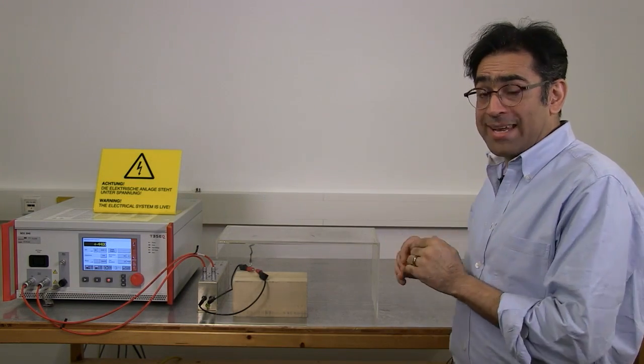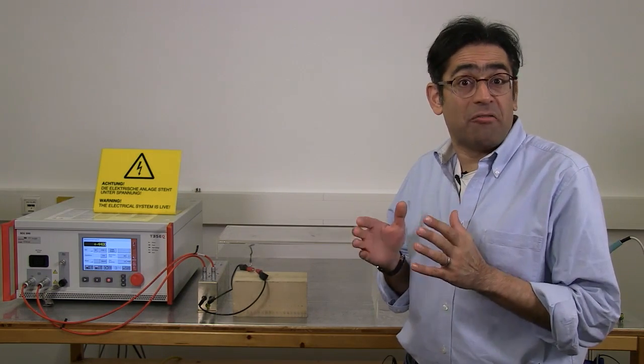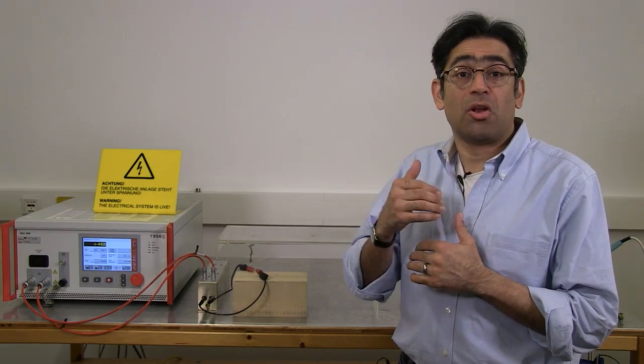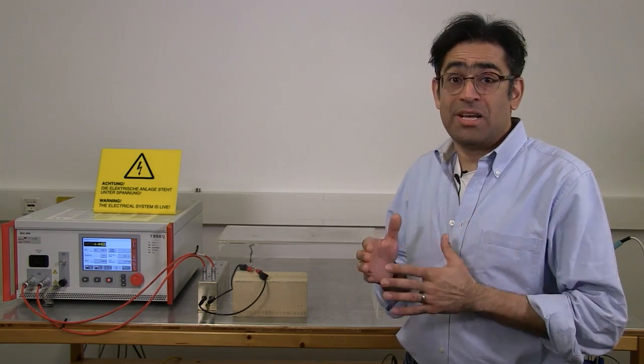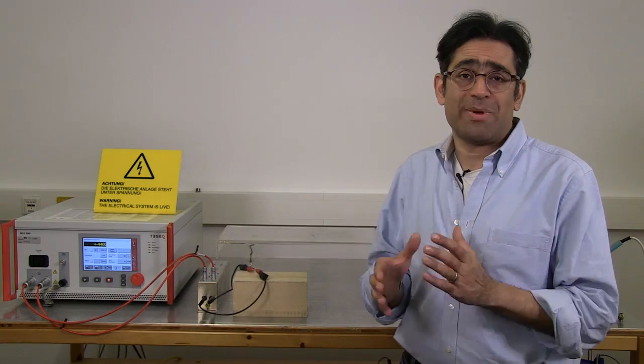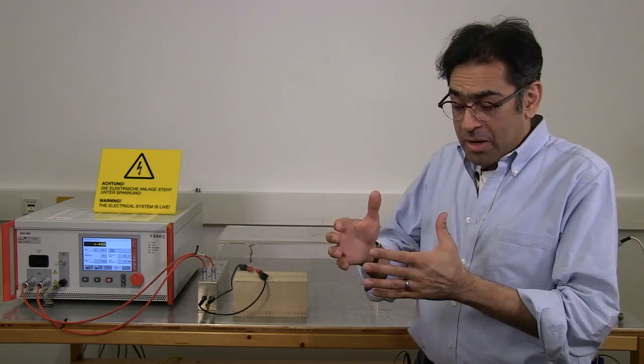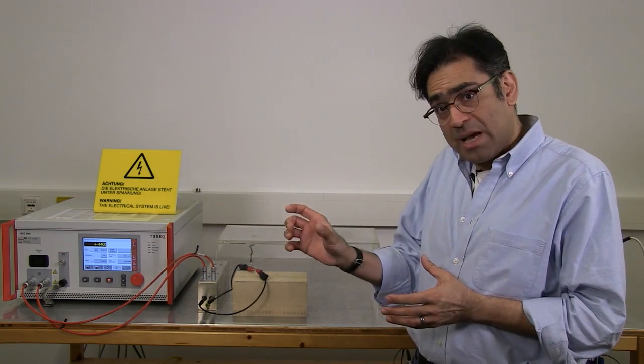The burst test was to emulate the impact of perhaps relays closing and chattering, the bounce on switches and the sparks that you may be getting. What we are going to look at now is the surge test. Now the surge test is designed to emulate perhaps the impact of a lightning strike on long cables. As you can imagine, this test can be quite dangerous because it has got a very large amount of energy that you are delivering.